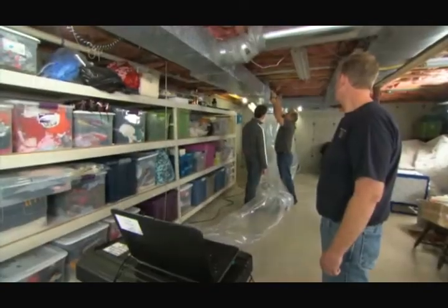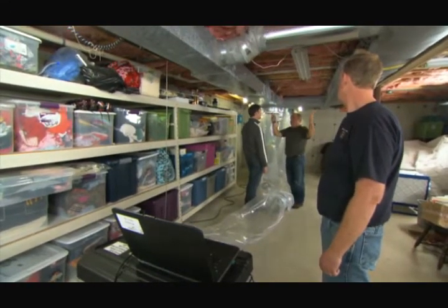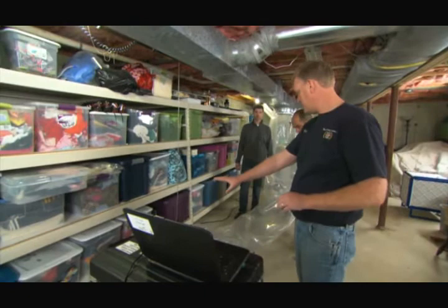So with this hole and the window screen over it, I've simulated some of the duct leakage you have upstairs in the building. So we all set to go, Steve? We are. Let her rip. So we'll activate the machine. Okay. The fan will turn on, and it'll start to inject the sealant. Here it comes.